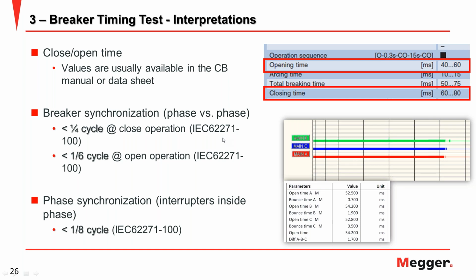For closed operation, a fourth of a cycle: if 50 hertz means 20 milliseconds, divided by 4, 5 milliseconds maximum difference for closed operation, and for open operation 3.3 milliseconds. If you have a difference of more than this specification, you need to do an investigation.